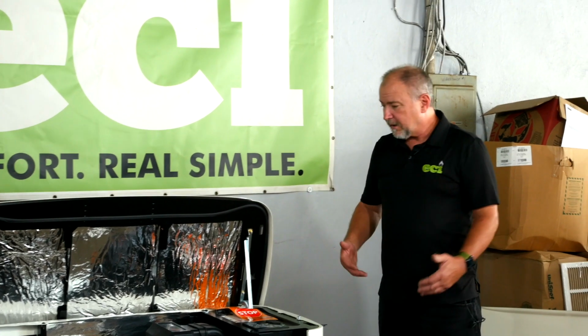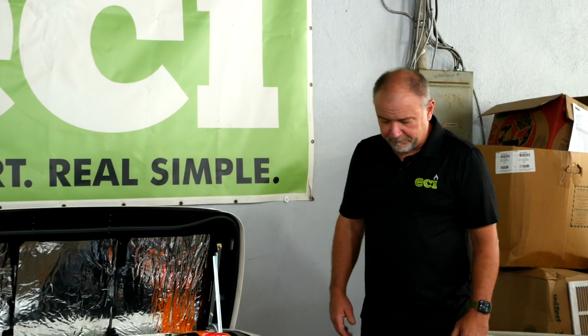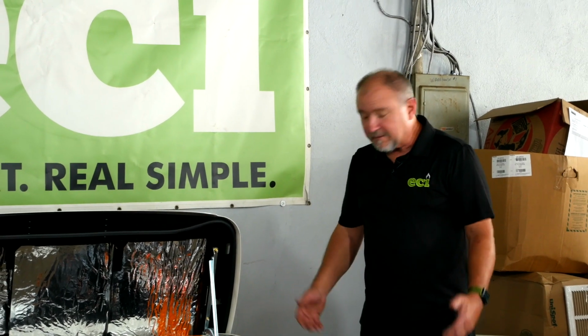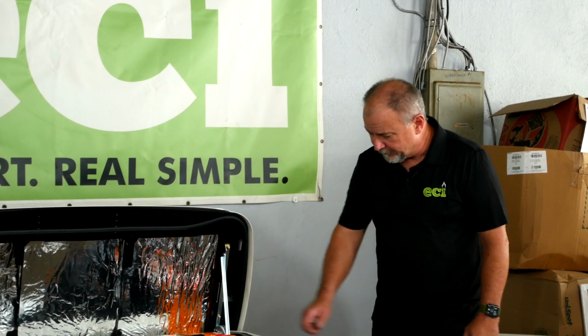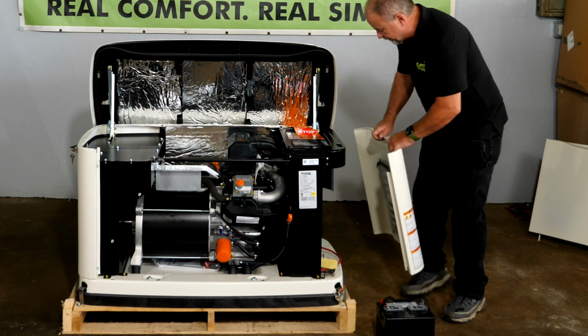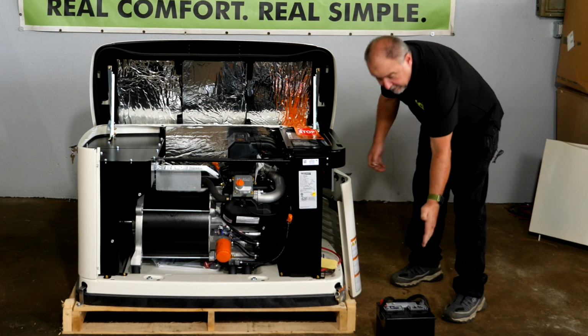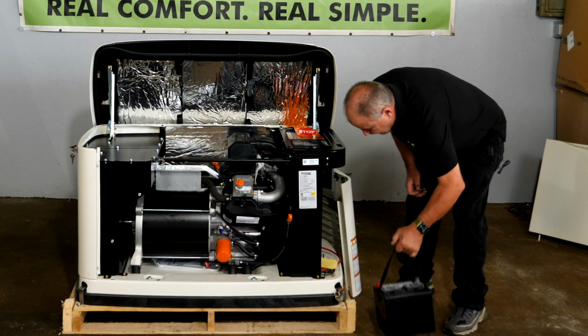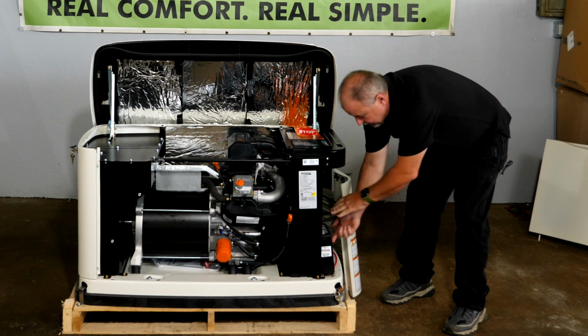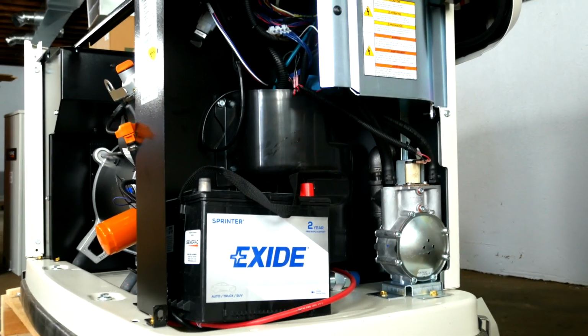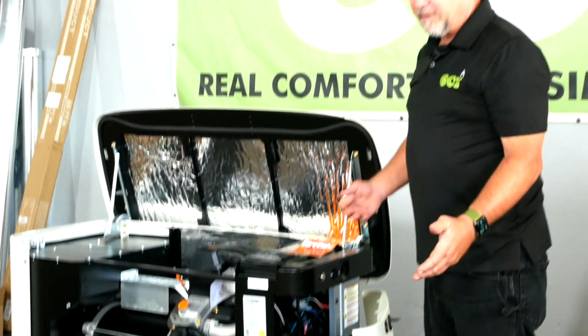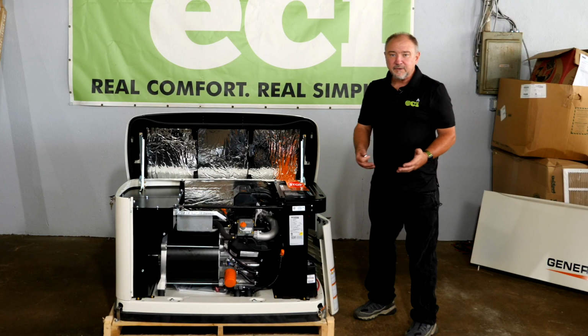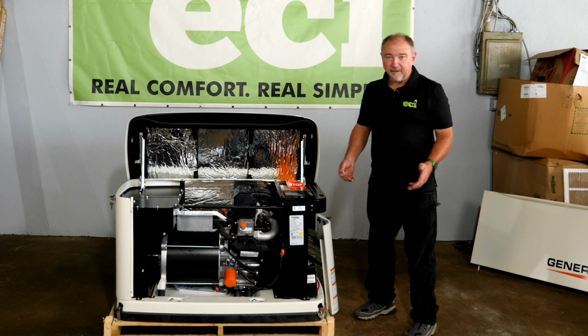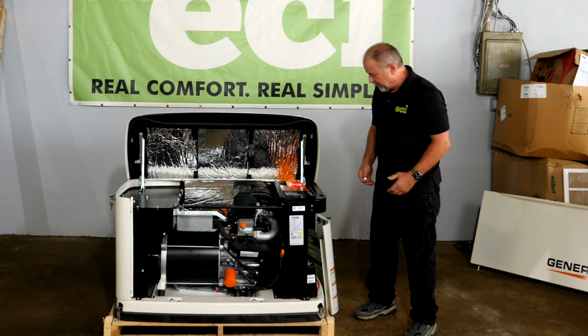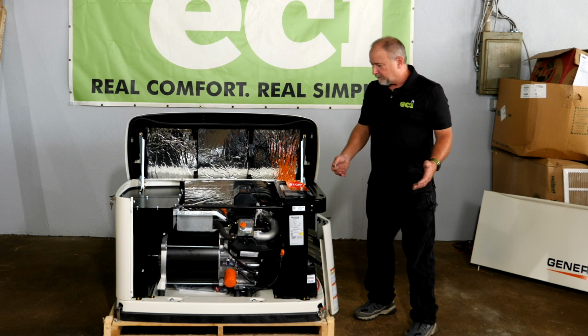When we lose power to the house, we need something to start the generator—it uses a battery similar to the one in your car, which sits in a compartment here, with the generator battery in a compartment over there. The battery needs to be checked and replaced every 5 years or so as needed, and we make sure the connections don't have corrosion, just like a car battery, so it's reliable and starts when you need it.